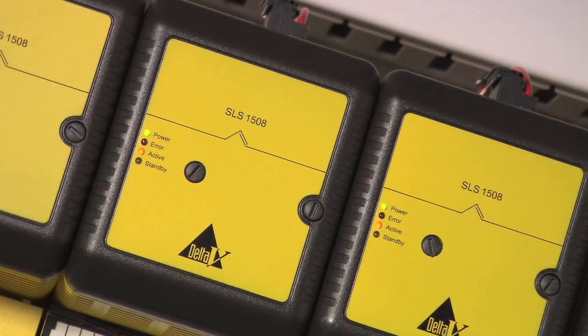DeltaV SIS is the only safety logic solver with integrated HART diagnostics to detect smart field device malfunctions and automatically adjust voting logic to avoid spurious trips. At the same time, Plantweb alerts with pinpointed diagnostics information are provided so that field device status is clearly visible to operations.